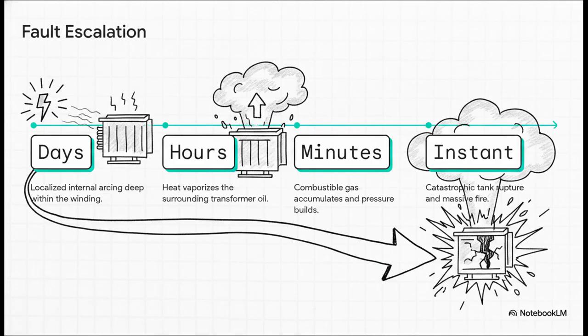It starts with just a little localized arcing deep in the winding turns, which could go on for days. The arc is so tiny the electrical relay is totally blind to it. But that heat is vaporizing the surrounding oil. Give it a few hours and you've got combustible gases. Within minutes, that gas accumulates, the pressure spikes, and if you don't catch it, boom. You are looking at an instantaneous tank rupture. We absolutely have to intervene way back at step 2 or 3.